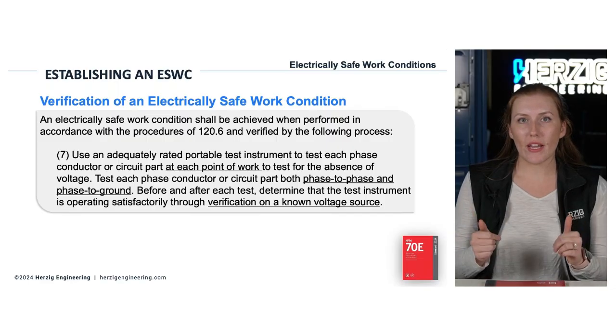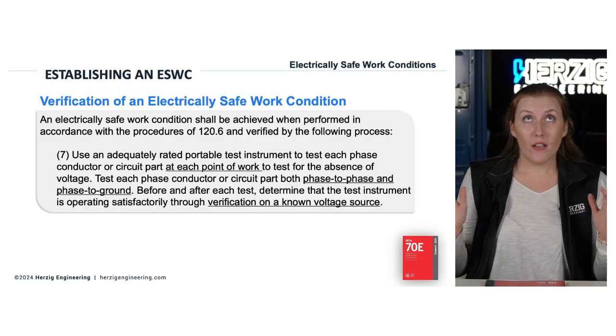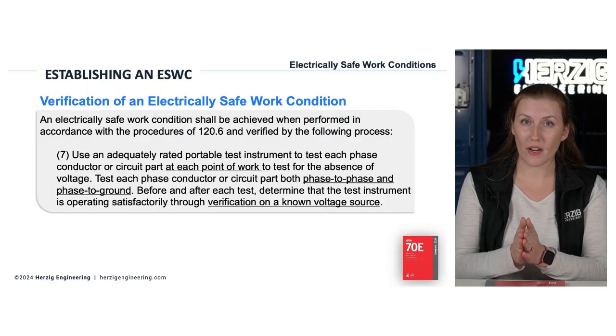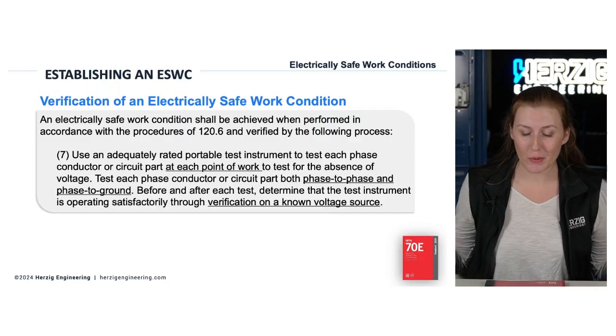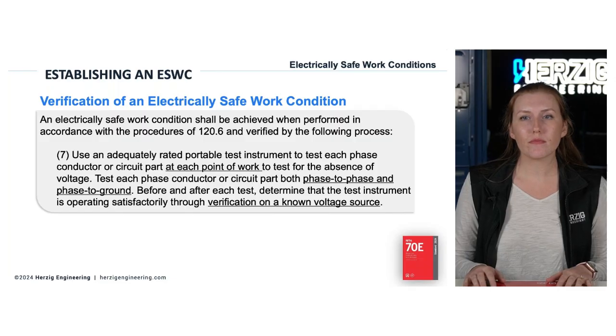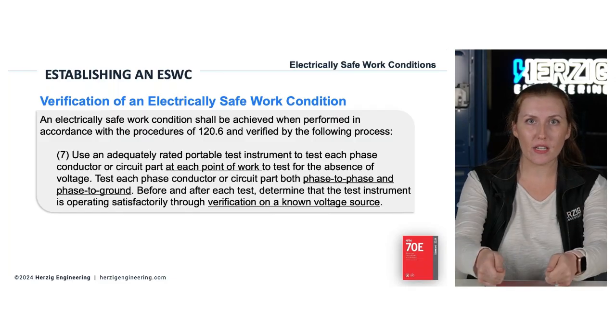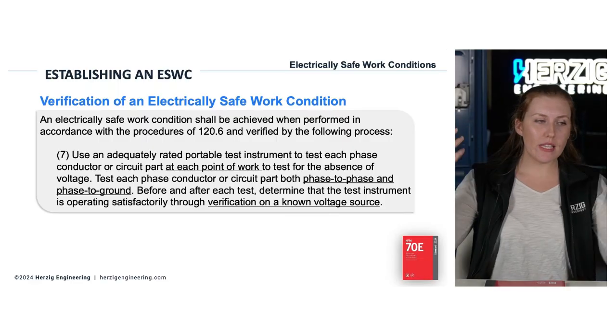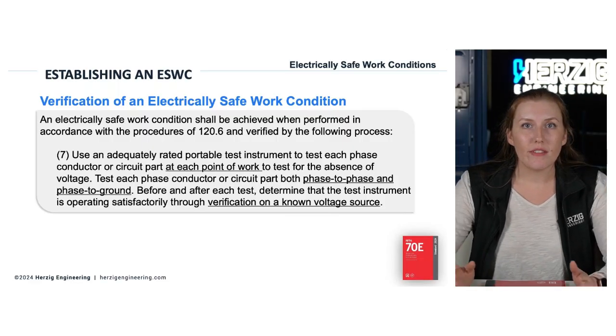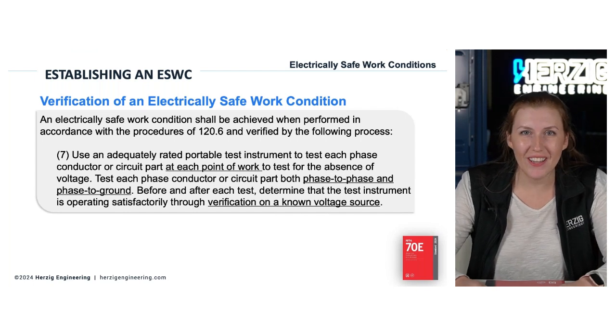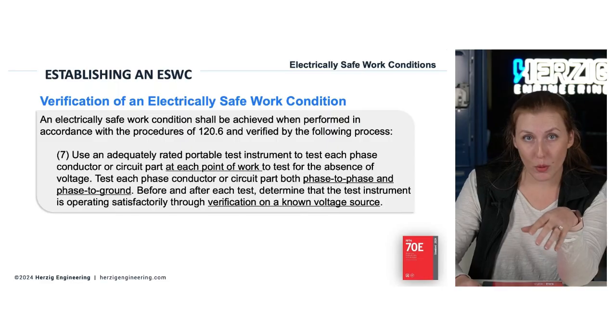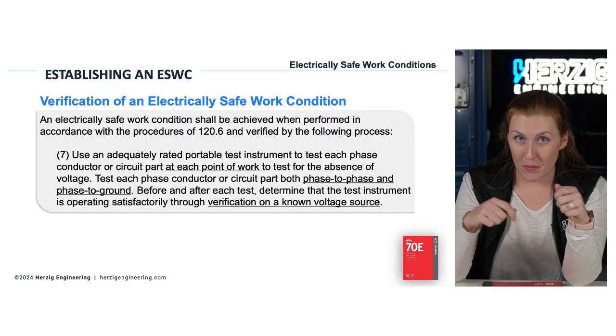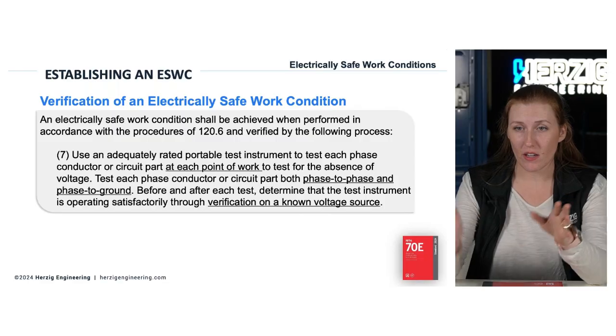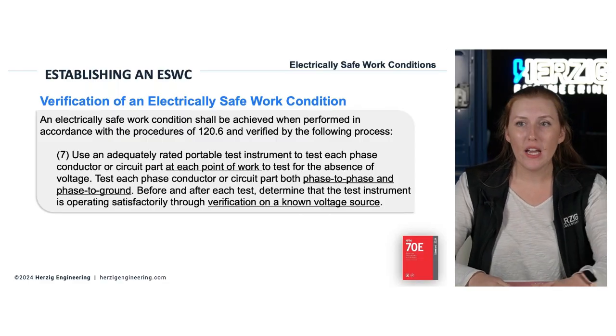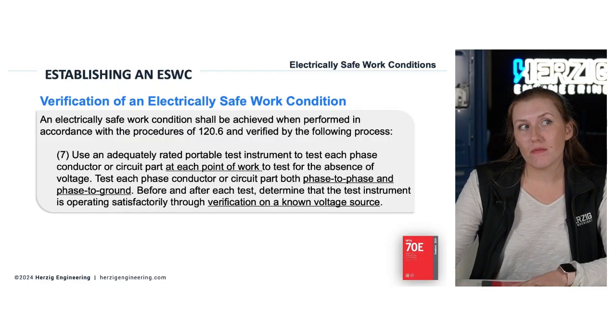So if you ever see someone locking out equipment and then they grab their meter, and let's just say that they're wearing their PPE and have their boundaries, so everything else is implemented properly, and they get their meter out and they put leads on equipment, and they're like, okay, yep, it's 0, and they start to doff the PPE, they've just skipped 2 to 3 steps because you're supposed to check at each point of work. So A to B, B to C, A to C, A to ground, B to ground, C to ground, all the phases, where they're actually working, and check that their meter is working itself.